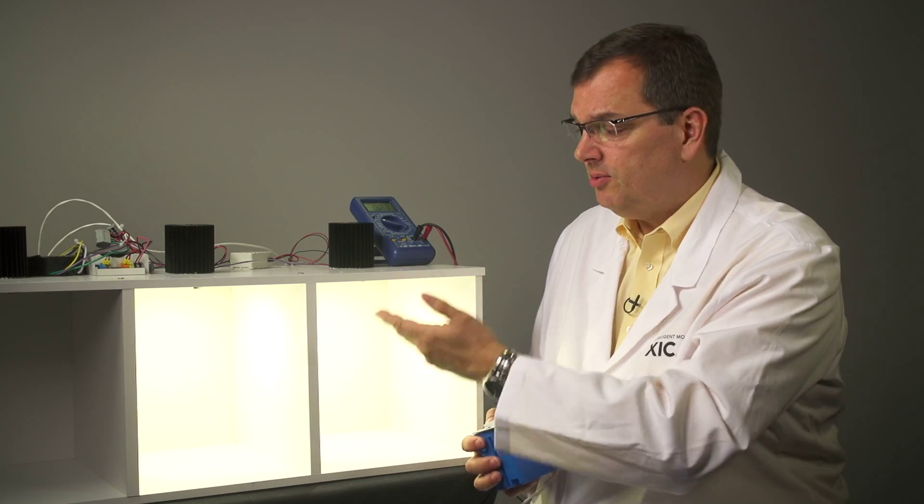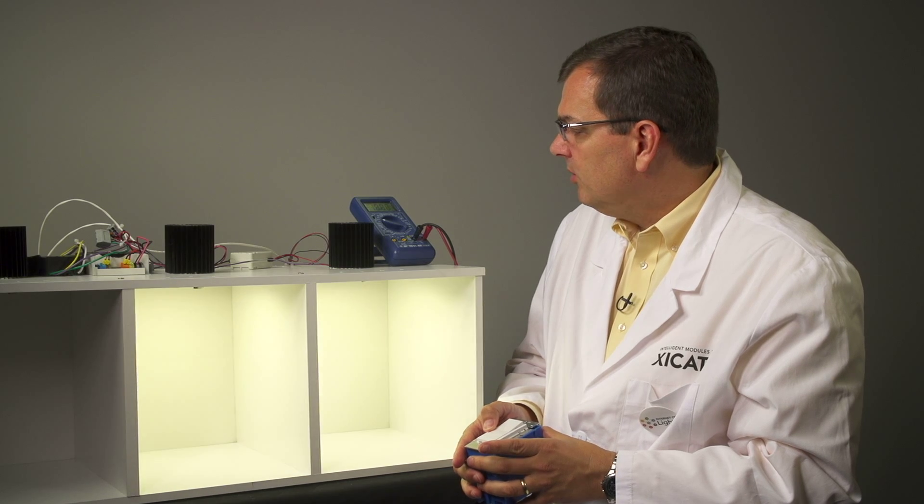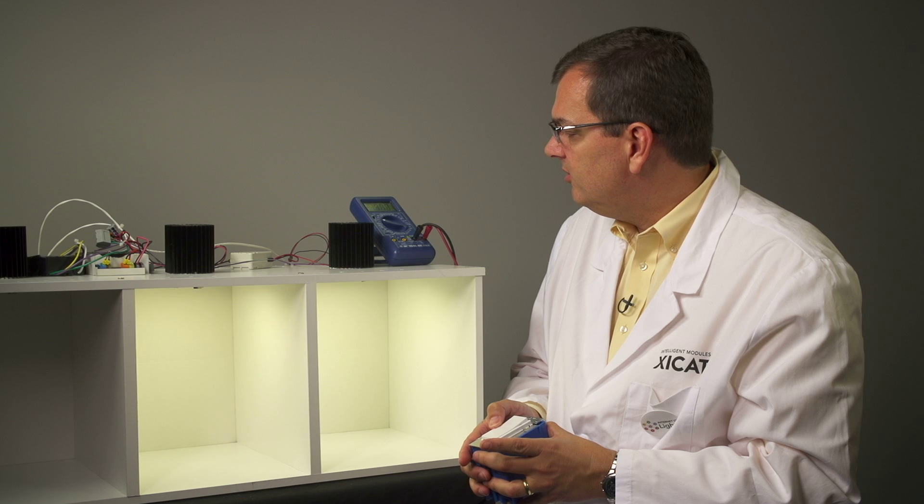Now let's look at the control system range. Right now we have it at full-on and we'll take it down. We're at about three and a half volts. They look pretty consistent.